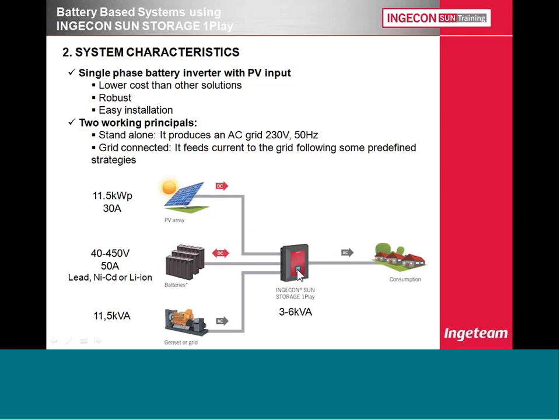In addition to these two renewable sources, let's call them renewable, even though this might not be renewable at all, it can work as a renewable source because you can have blackouts quite frequently, or very long blackouts throughout the day. In those scenarios where you have the grid but it's not very stable, you can always use this inverter, and when you have those disconnections, you can always connect the batteries to feed your loads. So the loads don't notice that there's no grid at that particular moment, because your inverter is producing the grid itself.